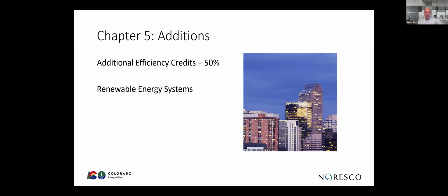One other thing on the addition sections I want to point out is section C405, your additional energy efficiency requirements section, where you have to have so many credits. If you're doing an addition on an existing building, you don't have to get all the additional energy efficiency credits—only 50% of the credits required based on occupancy and climate zone. Also, you must comply with the renewable energy systems, but only for that addition part.